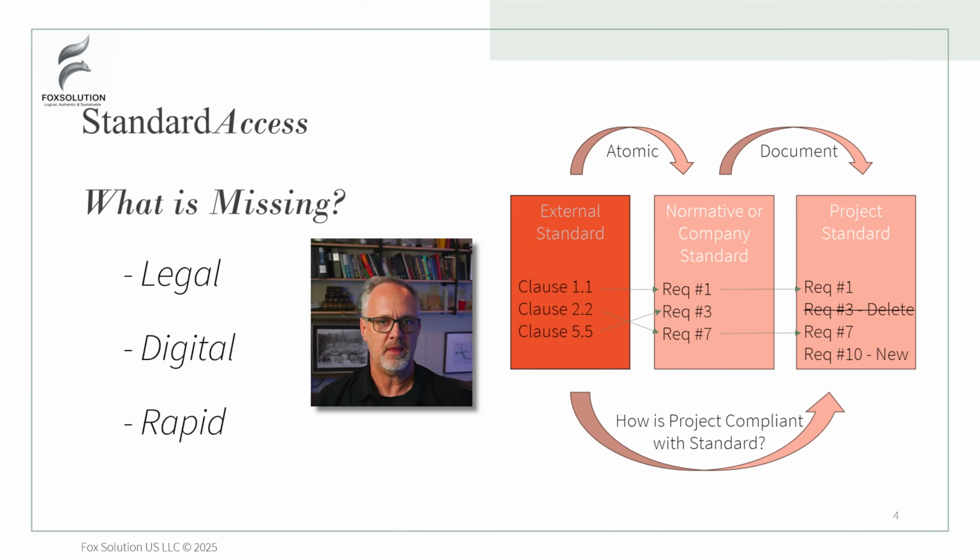And this system, as it's typically deployed in companies with documents, is incredibly slow. Usually what you'll end up with is a global process owner who gets assigned a standard for a product type, and there's usually more than one global process owner because you have different types of products in a company. And when a standard changes, usually what happens is they get an email that says, okay, what's the impact to all the products under your management for a change to the sterilization standard? So they have to go through, first of all, and figure out what's different, get a red line of the standard. Then they have to know what products are impacted by that revision of the standard, not any revision, that revision of the standard. And then they have to say, okay, what is the testing that would have to be done to bring all the other projects up to compliance?